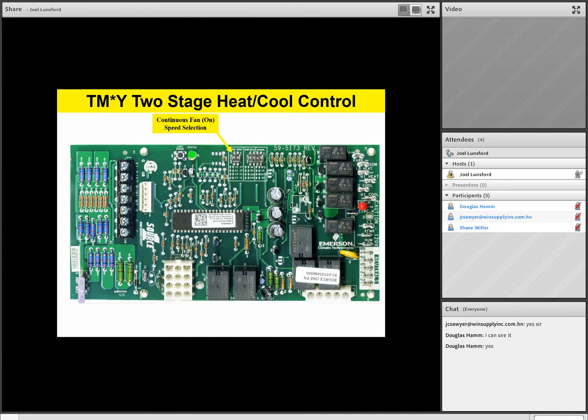Okay. The next little bank of dip switches is our heating off delay. We've talked about that before. You're going to set those dip switches up according to how long you want the fan to run after the call for heat goes away. So that's our heating off delay blower selection. And again, if you take a look at the graphics closely, you'll see it's 60, 90, 120, or 180 seconds that the fan will run after the call for heat goes away before it shuts off.